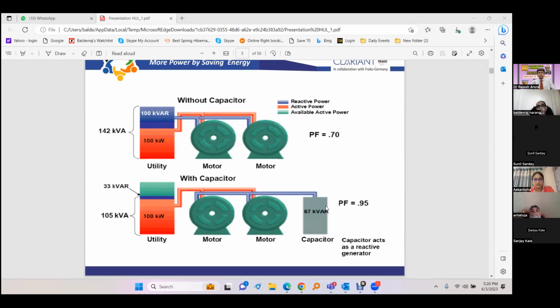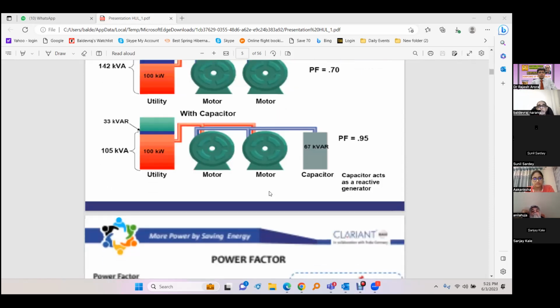And then suppose we put in the power factor improvement capacitor. Suppose we improve the power factor to 0.95. We need to put in 67 kVAr. Still, we are importing another 33 kVAr from the grid. So suppose we have unity power factor, we will not be importing anything from the grid. And this is the practice today. Almost negligible reactive power is being imported from the grid by industry.